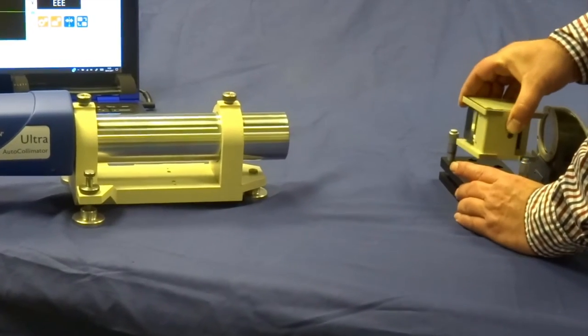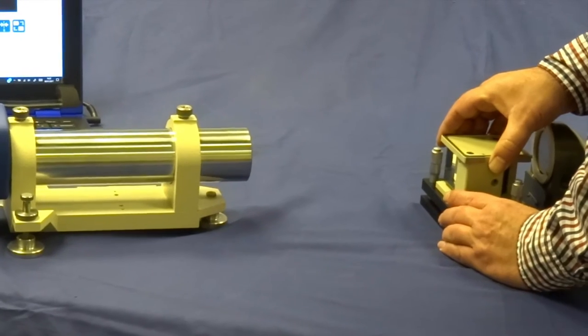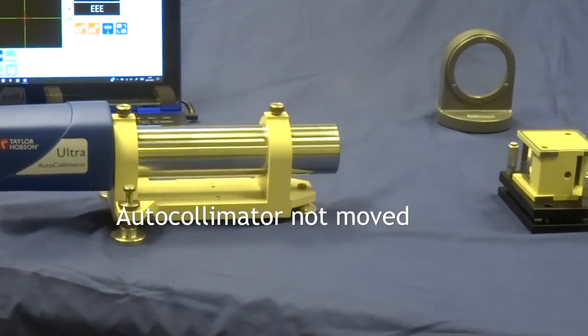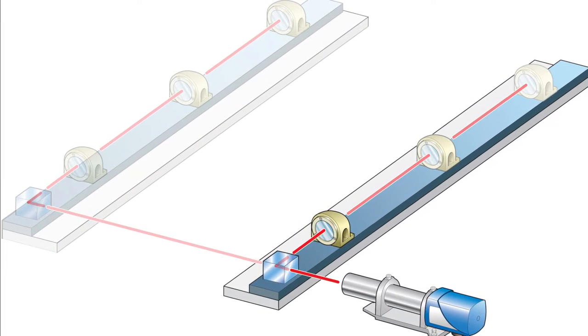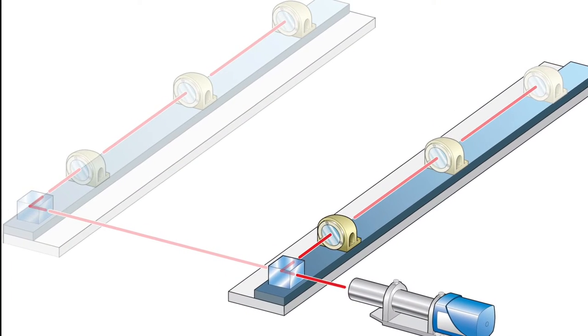Now we must insert the optical square and bend the light through 90 degrees. It is hugely important that the autocollimator is not moved when we measure the second slideway, as this must act as a datum.